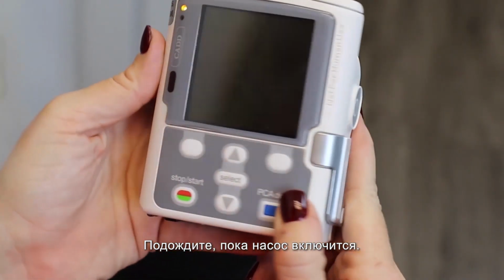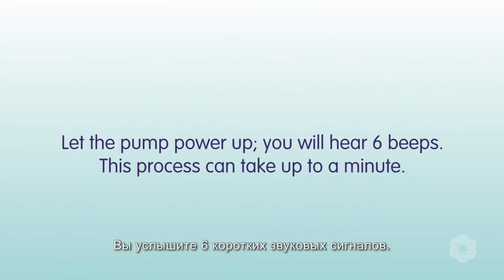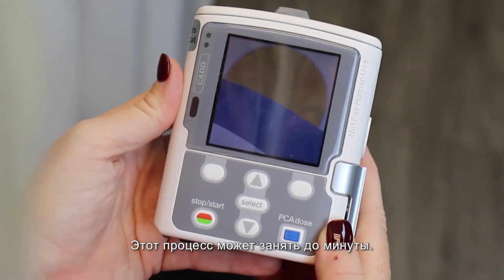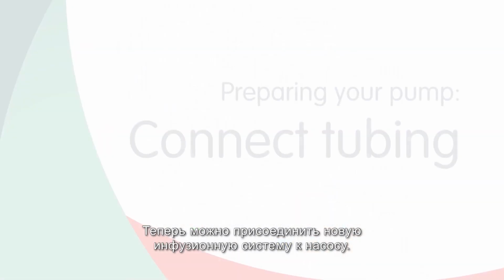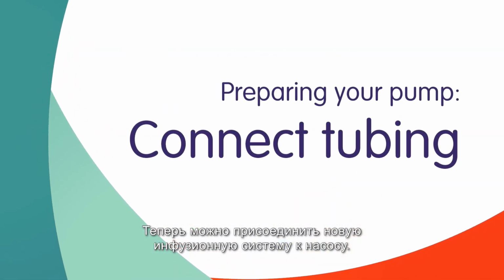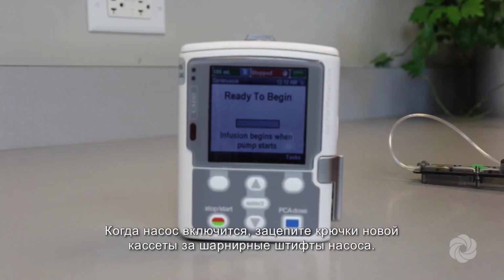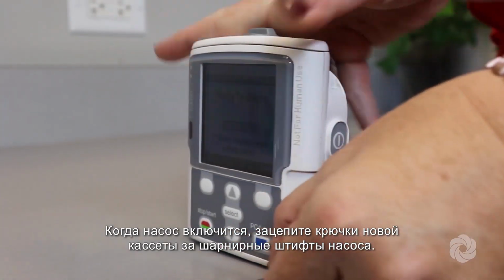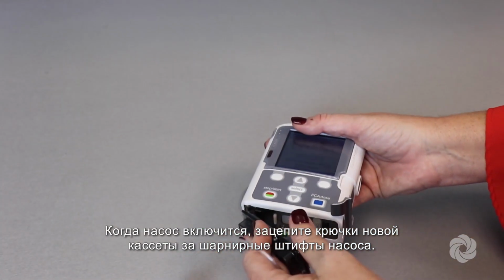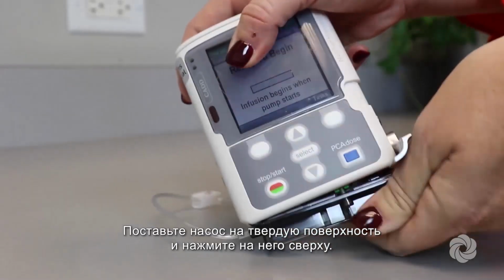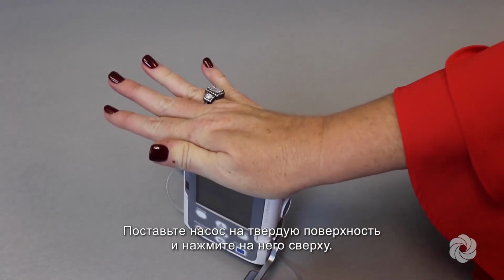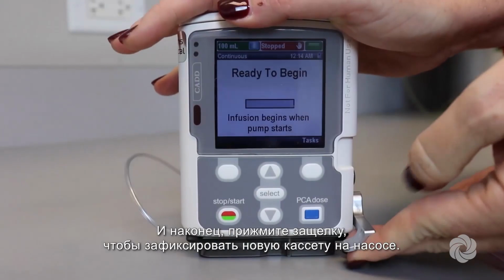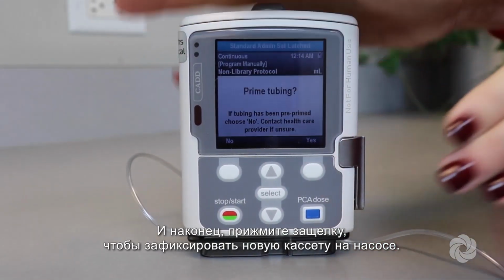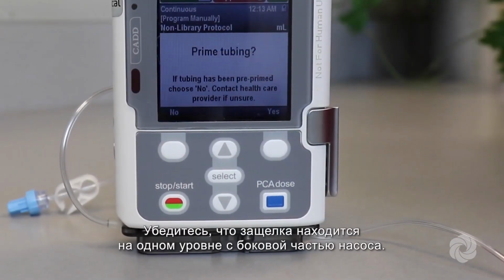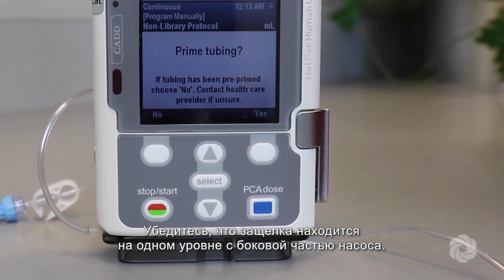Let the pump power up. You will hear 6 beeps. This process can take up to a minute. You are now ready to connect the new tubing to the pump. With the pump powered on, insert the new cassette hooks into the pump's hinge pins. Place the pump on a firm surface and push down on top of the pump. Finally, press up on the latch to lock the new cassette to the pump. Ensure the latch is flush with the side of the pump.